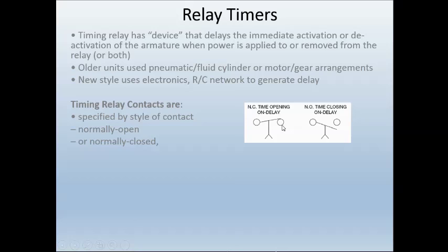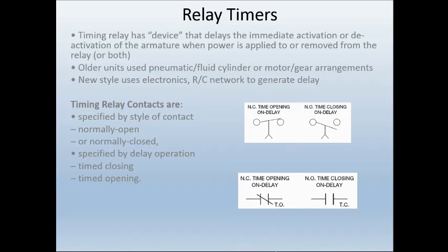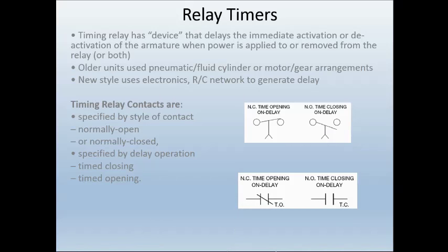Timing relay contacts are specified by the style of contact — you have your normally open and your normally closed. You can see in its normal position this contact is open, and this one here in its normal position the contact is closed. We also specify by the operation: timing closed or timing open. The direction of the arrow here will help us indicate which direction the timing function is going to happen.